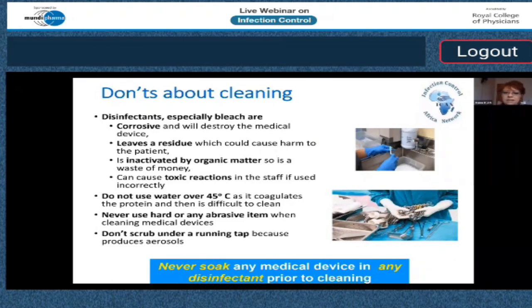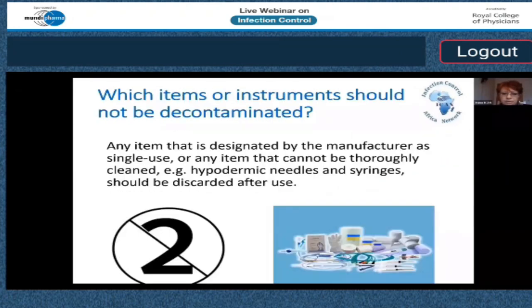So if you look at the bucket inside the basket, there is a level of water, and we want them to immerse the instrument under the level of water and brush lightly under the level of water. When they take it out and dry it a little bit, there's no possibility of splashing, so then they are quite safe. And also, never soak this in any disinfectant, as this could be quite detrimental to the instrument and to the patient.